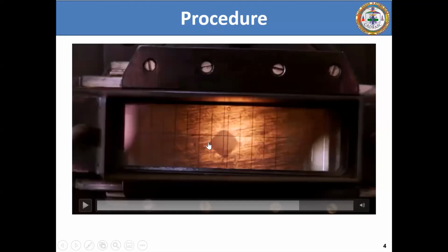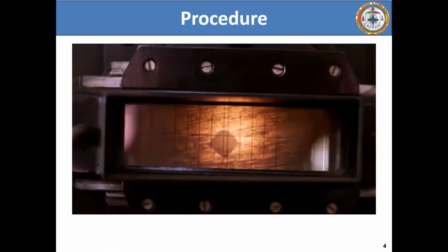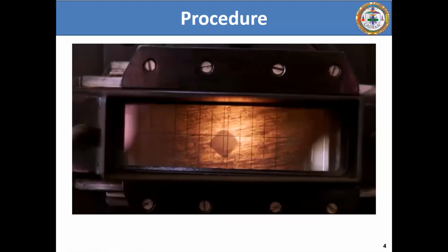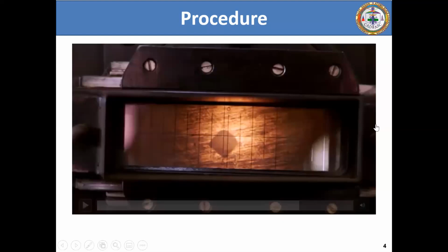Rather, there are four curves. I mean, some part of the square has been eaten up, so you will see this curved, this curved, this curved, and this again curved. So it also happens. The ultimate requirement is that we have to keep monitoring that the Vickers micro indenter is not worn out. Once it is worn out, we have to service it or replace it. This is the Vickers micro indent that you see in that microscope.